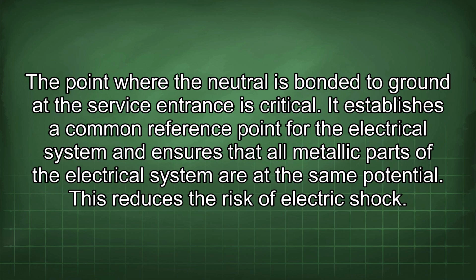The point where the neutral is bonded to ground at the service entrance is critical. It establishes a common reference point for the electrical system and ensures that all metallic parts of the electrical system are at the same potential. This reduces the risk of electric shock.